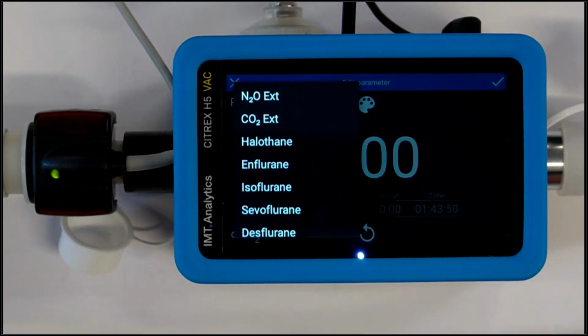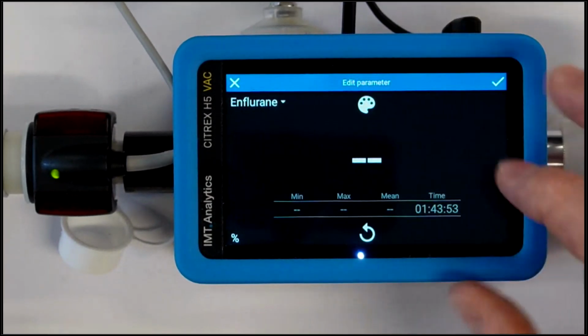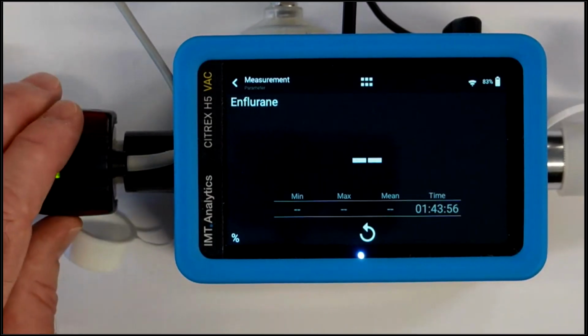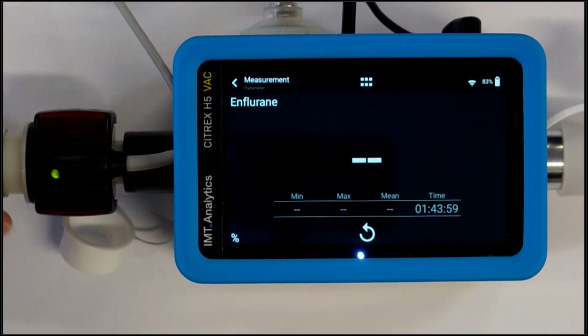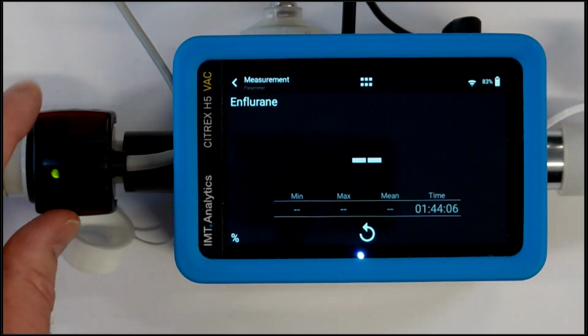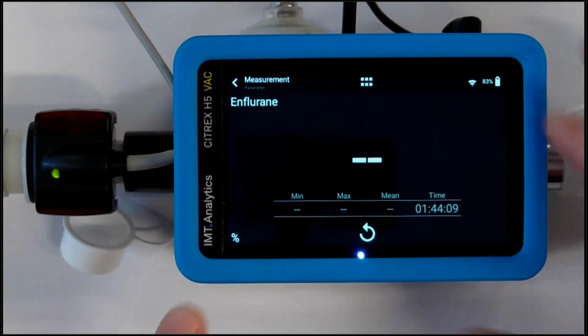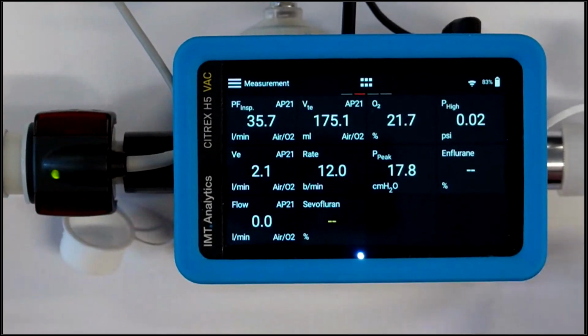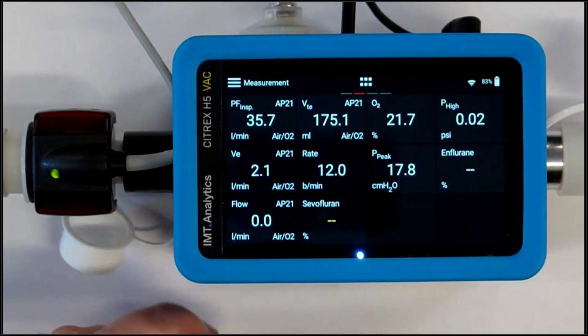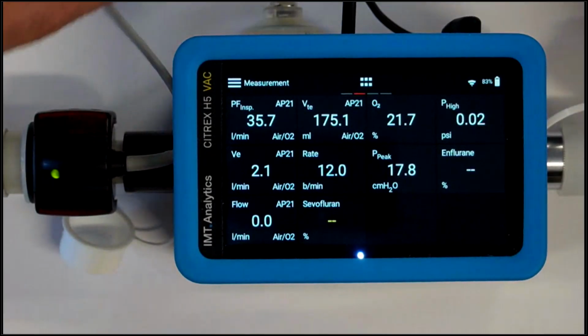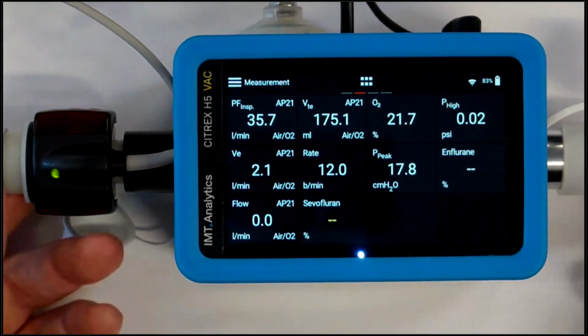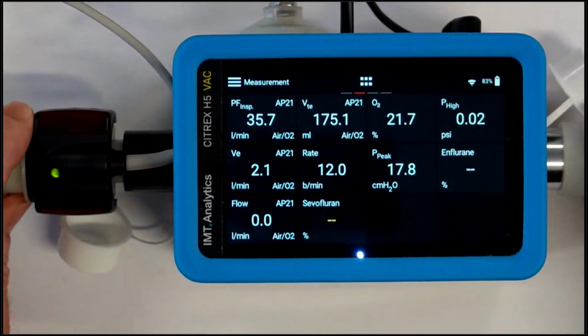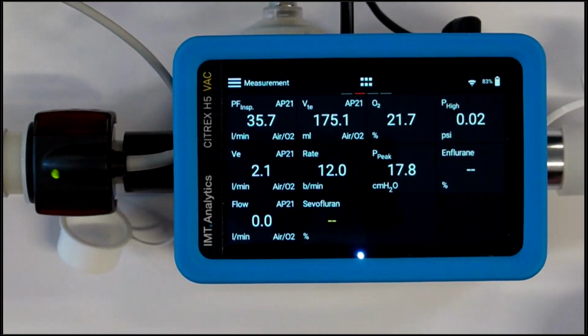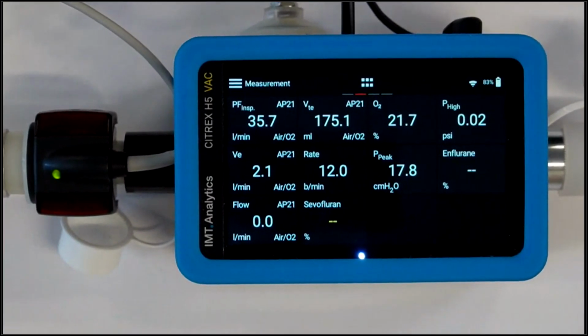And if I was actually delivering those gases here, we would see the concentration of that gas with each breath. Because this is a main flow analyzer, which means no gas has to be taken out for side stream. It can actually measure breath by breath the concentration of the gas that's there. So you can actually have multiple gases, and depending upon what one's being delivered, you can see it on the screen. So all in all, very easy to set up, very small but very powerful test system for your ventilator and anesthesia requirements. Okay, next I'll change this up just a little bit.